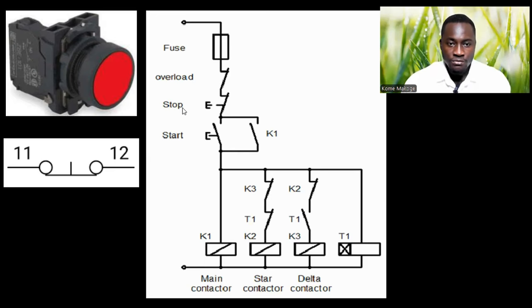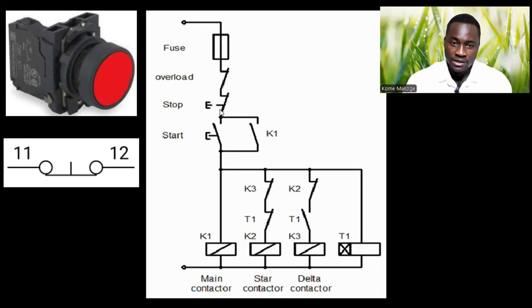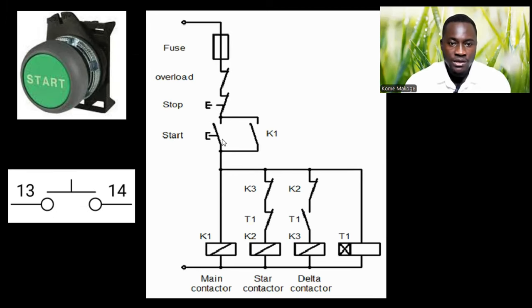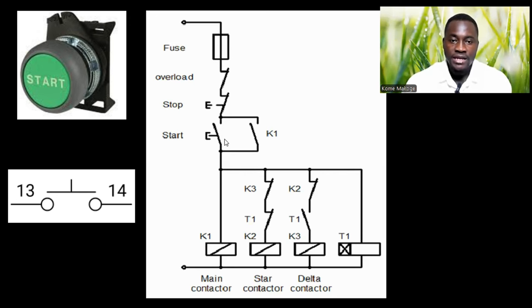The next point is the stop push button. We are going to be using the normally closed push button as a stop push button. When you press the push button, when your hand is released, the contact retracts back to its normal state and closes the contact again. The next is our start push button, which is a normally open contact. When you press it, it extends and closes the contact. When your hand is released from the push button, it retracts back and goes back to its normal open position.